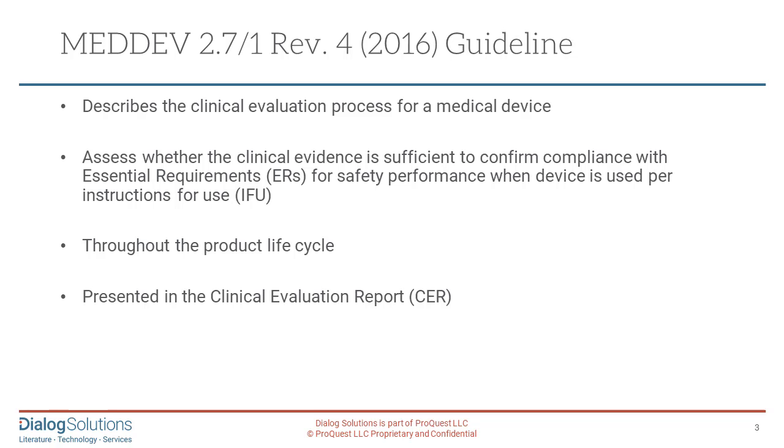MEDDEV 2.7/1 Revision 4 describes the clinical evaluation process for a medical device and assesses whether the clinical evidence is sufficient to confirm compliance with essential requirements for safety and performance when the device is used according to the instructions for use. It's very important that this goes on throughout the product lifecycle — pre-approval, in use, and post-approval. For example, post-marketing surveillance of adverse events has been strengthened in the regulations, and all information needs to be presented in a CER or clinical evaluation report.